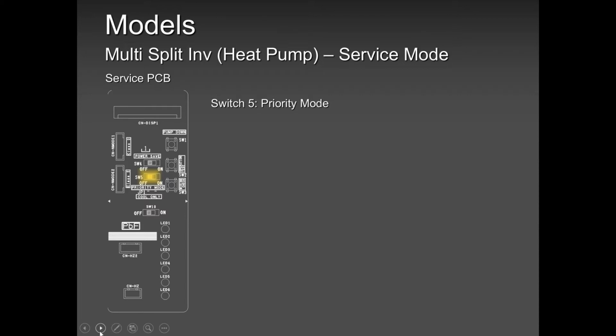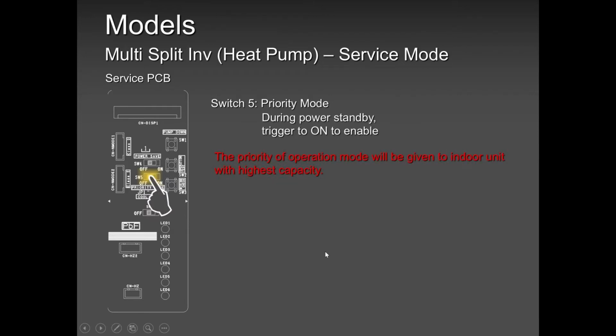And priority mode. What is priority mode? We have that button. You can use it if you want to, but so far in these 6 years with Panasonic, no contractor has used it. But again, if you have an option, you have it. So what it does, when you switch on the SW5, the priority of operation mode will be given to the indoor unit with the highest capacity. So in a system, let's say you have a 7, 7, 12, and 18. The person using the 18,000 BTU unit can change modes depending on what they want, while the others will be kept on standby. That's what priority mode does. I don't think this can happen, but again, if you want it to happen, you have that option. And if you're not sure or cannot remember, 2 or 3 months down the road, always give us a call.